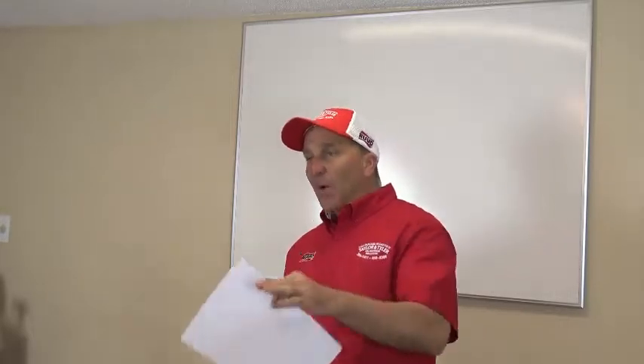And what this thing does basically is it kicks your compressor into gear. It adds another 370 volts to that compressor when it goes to start and pops it in its button, kicks it into gear. So now when your system goes to start, instead of that amperage pegging out to 116 amps, it might only drop to 30 amps. I went ahead and put one on it just to see what it would draw, and it drew 34 amps when I started instead of 116 amps.